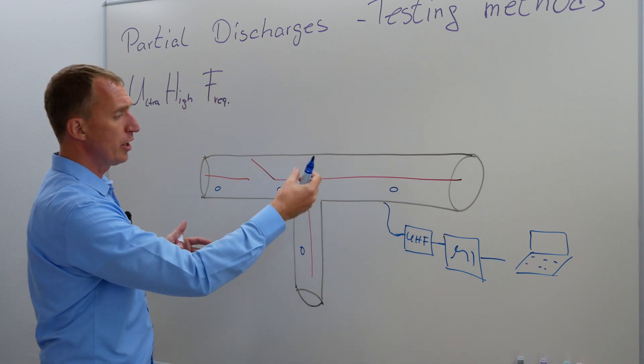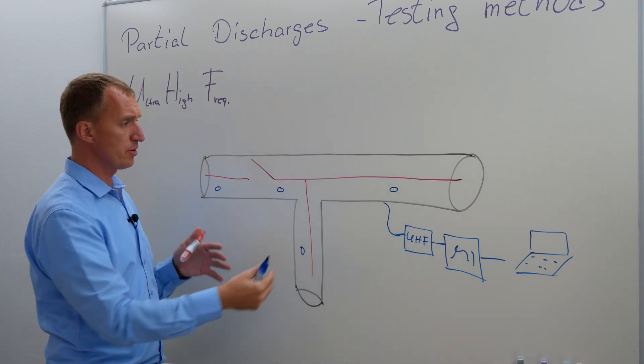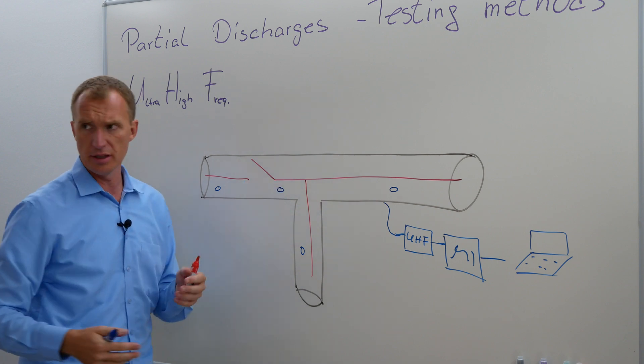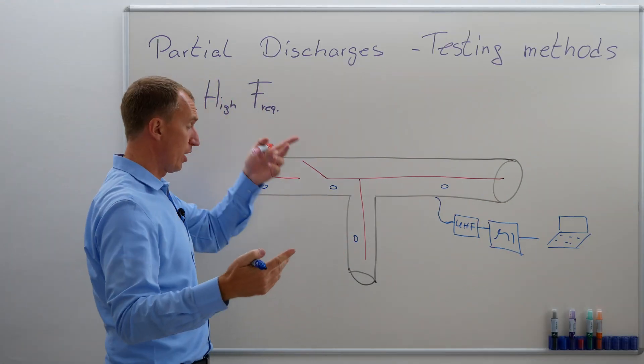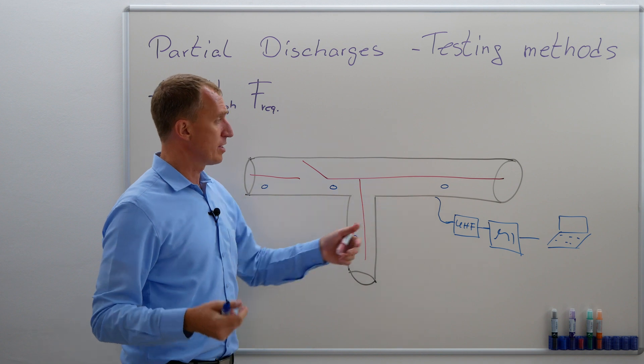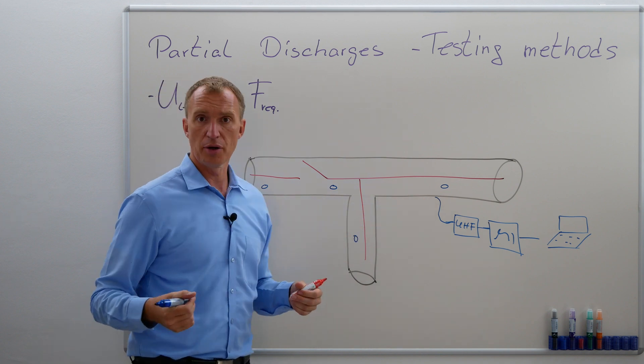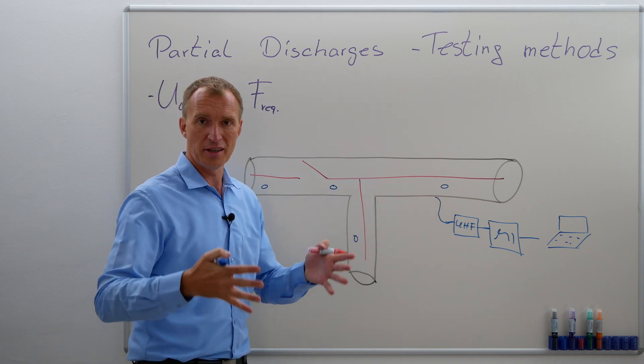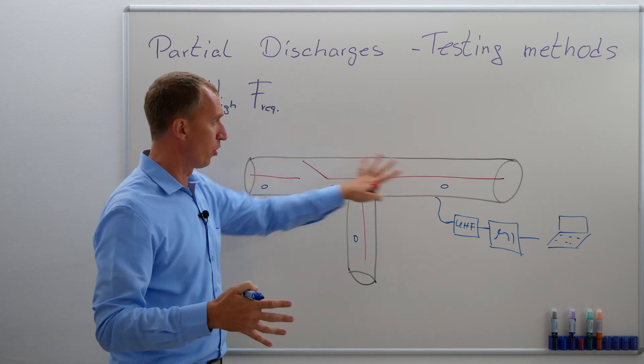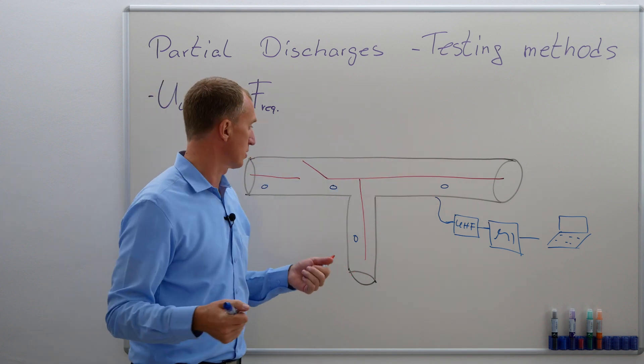Now, you can use UHF sensors in order to measure partial discharges, and here, once again, it's a different kind of frequency set, it's ultra-high frequency, and this allows you to have an idea about the GIS. You're literally using the case that it's already a shielded room, and it's kind of advantageous. There is a little bit of a downside.